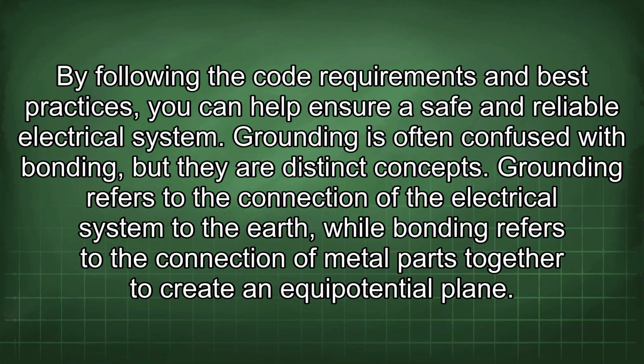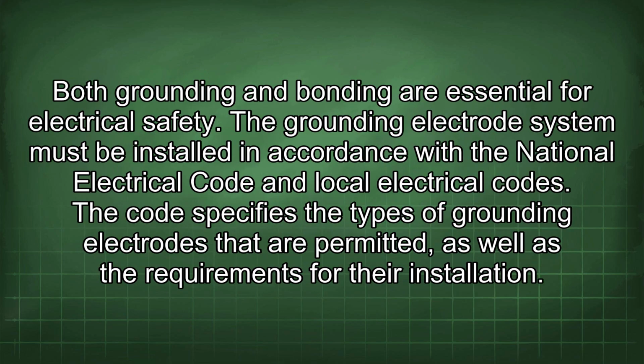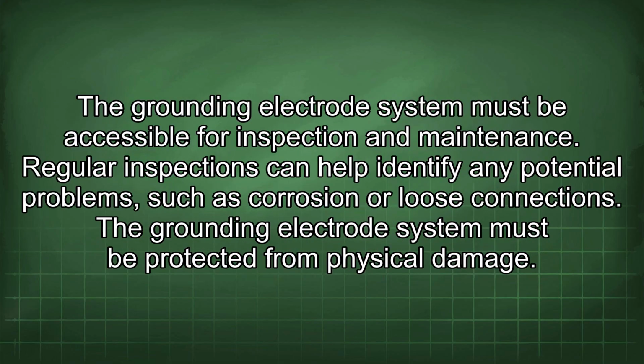Grounding is often confused with bonding, but they are distinct concepts. Grounding refers to the connection of the electrical system to the earth, while bonding refers to the connection of metal parts together to create an equipotential plane. Both grounding and bonding are essential for electrical safety. The grounding electrode system must be installed in accordance with the National Electrical Code and local electrical codes. The code specifies the types of grounding electrodes that are permitted, as well as the requirements for their installation. The grounding electrode system must be accessible for inspection and maintenance.